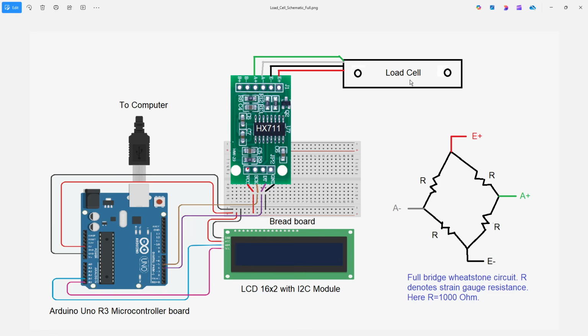The load cell has got 4 strain gauges attached to it. There are 2 strain gauges on the top and 2 on the bottom. The strain gauges are connected in this particular manner. So a full bridge Wheatstone circuit is being used. In here R denotes the resistance of the strain gauge. Here the resistance value is 1000 ohms.